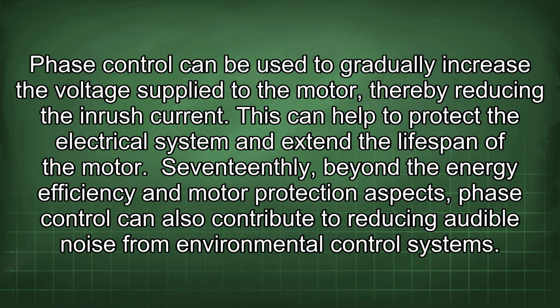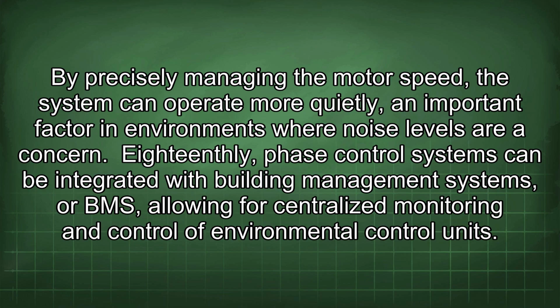17thly, beyond the energy efficiency and motor protection aspects, phase control can also contribute to reducing audible noise from environmental control systems. By precisely managing the motor speed, the system can operate more quietly, an important factor in environments where noise levels are a concern.